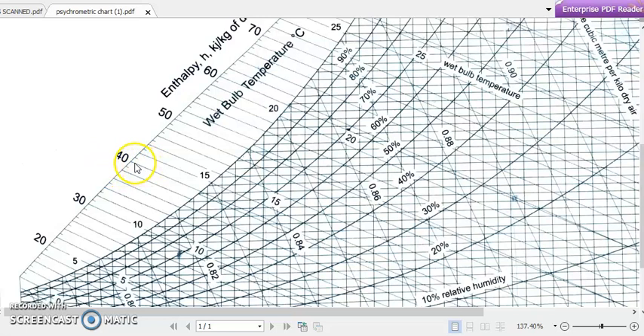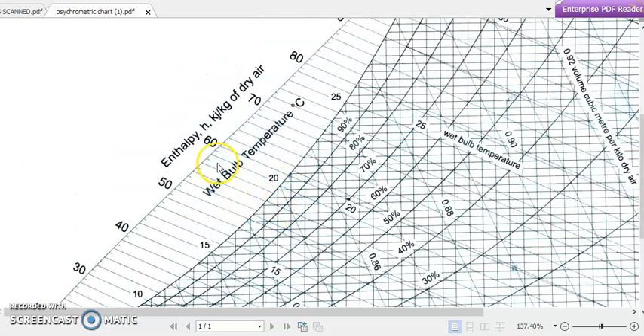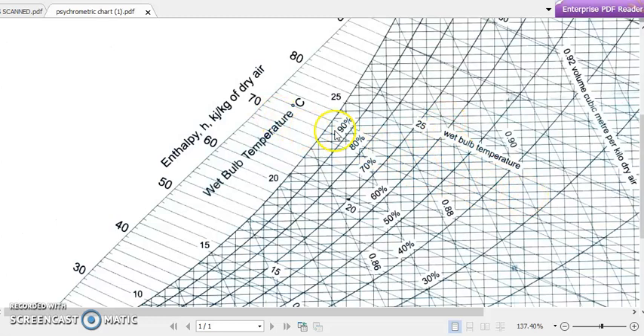To follow a specific enthalpy line, such as the 40 kilojoules per kilogram line, you follow that inclined line into the chart. A specialty of this psychrometric chart is that the enthalpy lines and wet bulb temperature lines are parallel to each other — both have the same inclination or slope. So we can use either enthalpy lines or wet bulb temperature lines interchangeably.